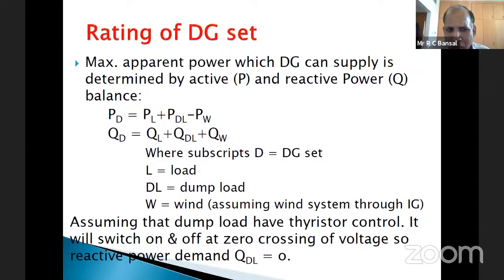The same applies for the reactive power rating of the diesel generator. It depends on the reactive power rating of the load, which can be inductive load or induction motor loads, so you need to know how much reactive power is required. If your dump load comprises inductive load, that affects the reactive power rating too.